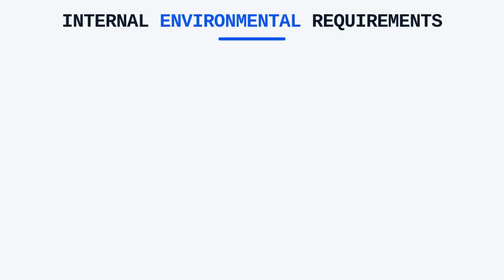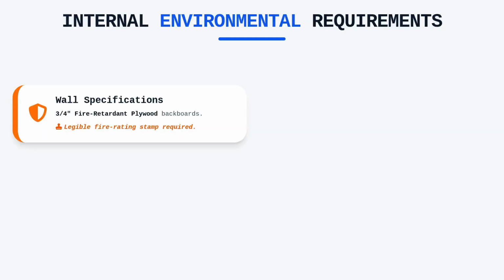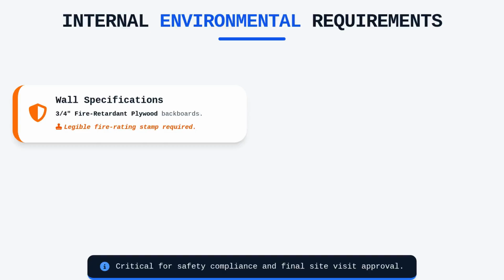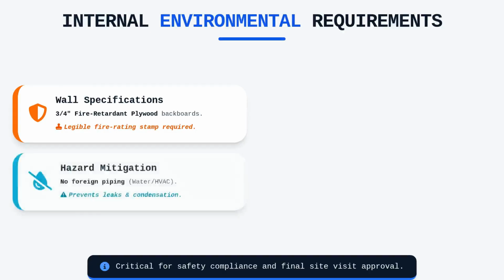Beyond floor area, the internal environmental requirements are just as stringent as the physical layout. Every wall must be lined with 3/4 inch, fire-retardant treated plywood backboards to allow for secure mounting of termination hardware and cross-connect fields. You must confirm that this plywood carries a legible stamp indicating its fire rating, as building inspectors will prioritize this safety feature during their final site visit. Furthermore, the space must be entirely devoid of foreign piping, such as water lines for fire sprinklers or HVAC ductwork, to prevent catastrophic damage from leaks or condensation.